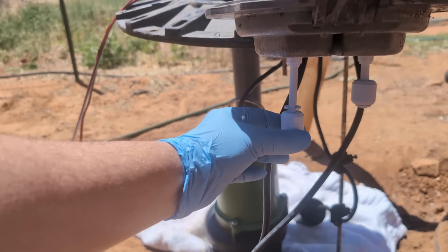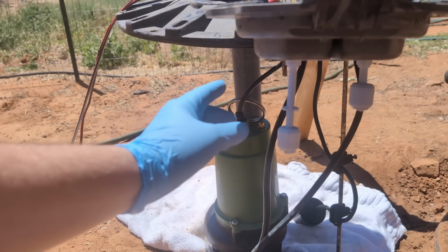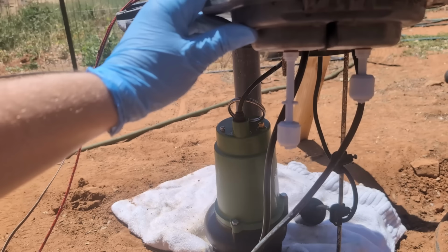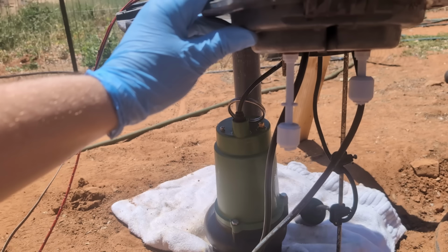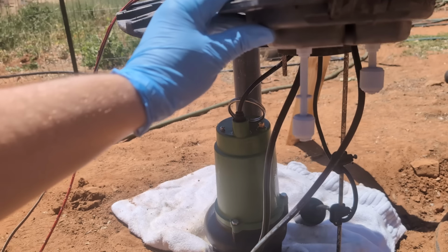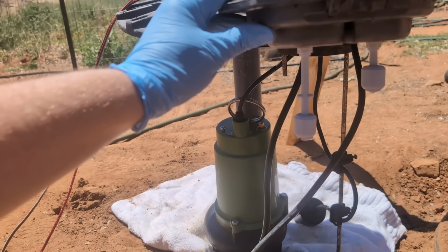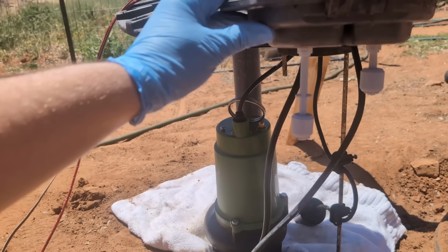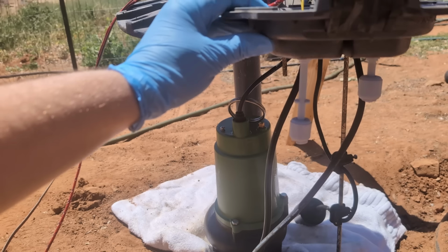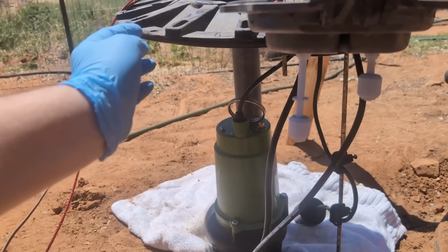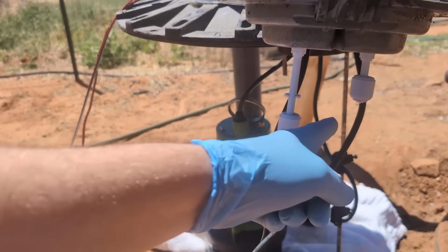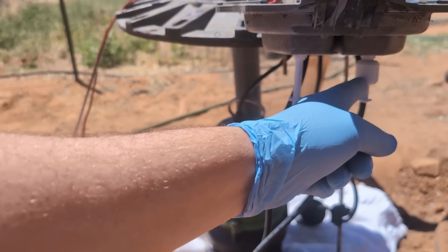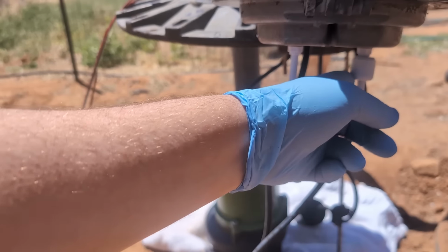It would go on and then off, on and then off, on and then off. So this one requires the software that I'm writing to turn the pump on for, let's say, 20 seconds, and then it just turns itself off. That is another normal condition for this to be running in. I actually wouldn't care at all if this pump ran on this for another 2 years. That'd be great. However, if it ever trips this one, it's game over. Get out here, fix it, find out what's wrong.